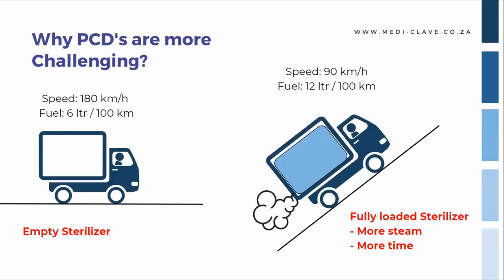In the beginning, steam sterilizer manufacturers were also objecting to the helix. It was showing failures, where the printer recording of the parameters was showing no failures. We all know that running the Bowie-Dick test pack is done without a load, as another one or a load may influence your test result. An interesting aspect, however, is that once a failure is detected by the batch control helix device, all other proof shows that there's nothing wrong with the steam sterilizer. This is based upon tests performed without a load. So the illustration is quite clear.